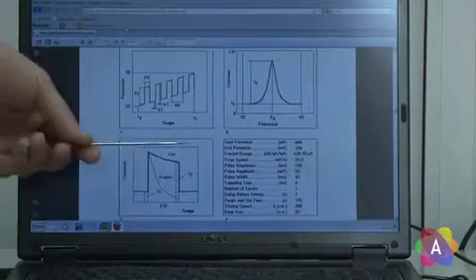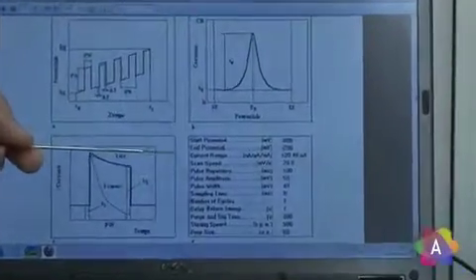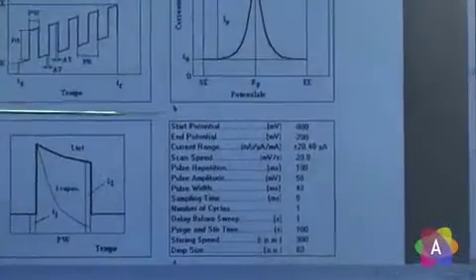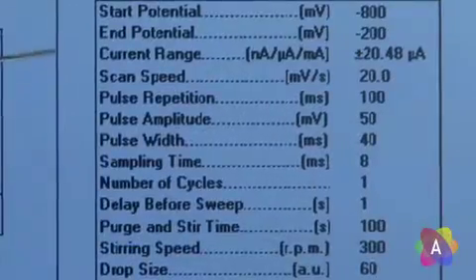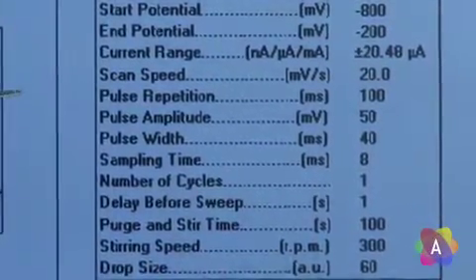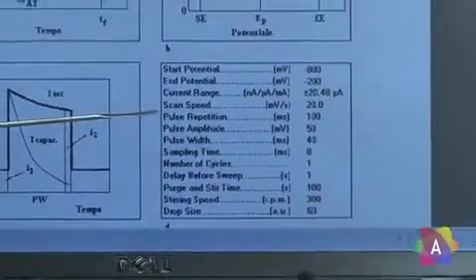The differential pulse scanning needs the following settings: the starting and ending potential, the range current, the speed of the scanning of potential, and the parameters of the pulse: time repetition, potential amplitude, time width, and the sampling time of the current before and at the end of the pulse.